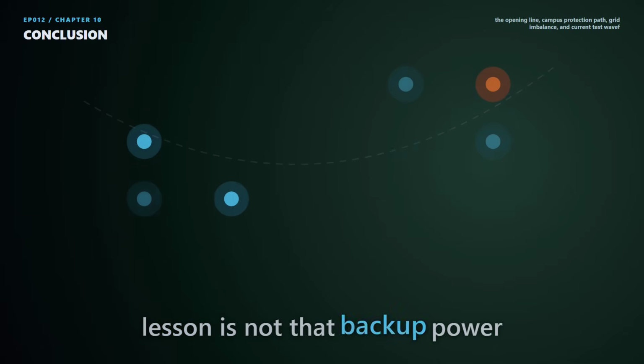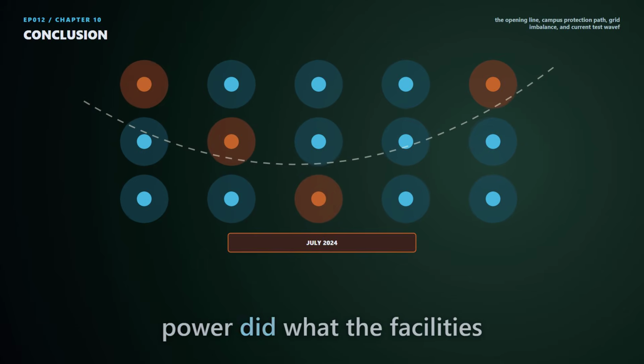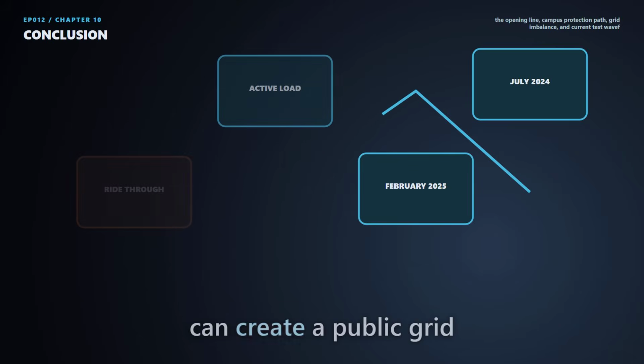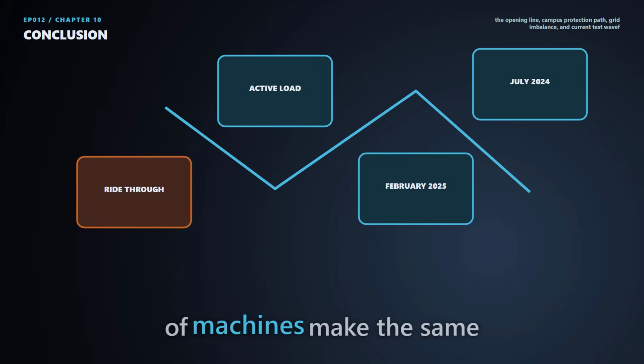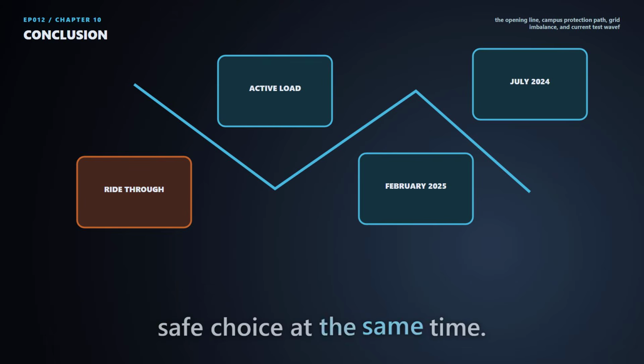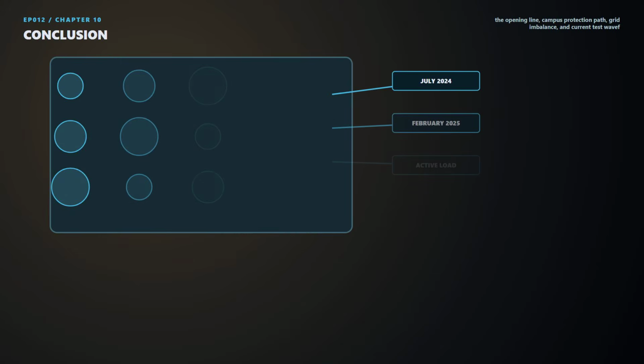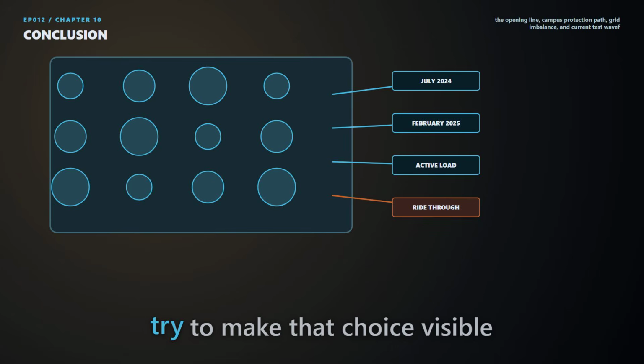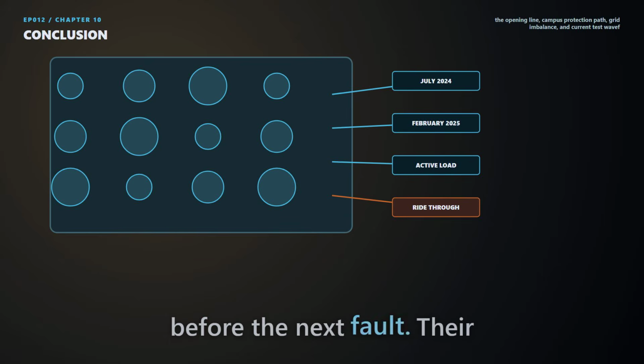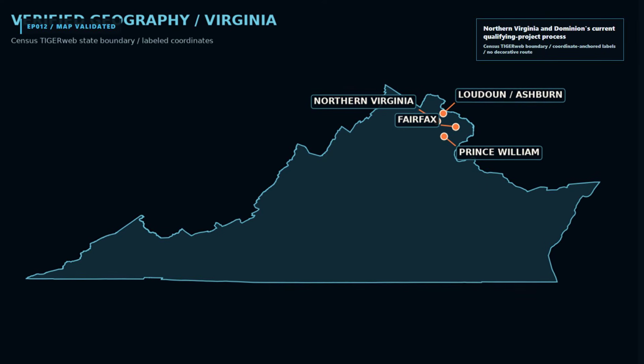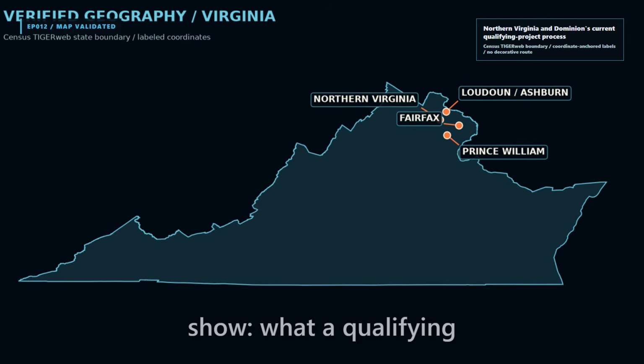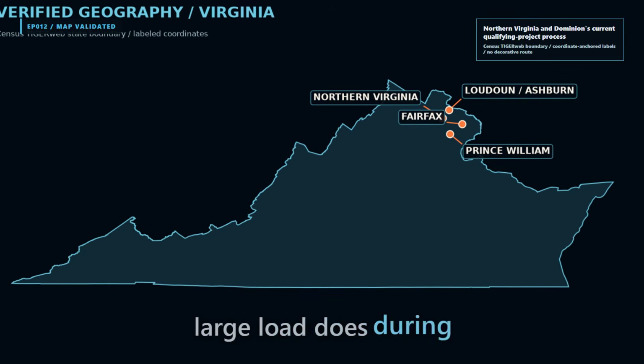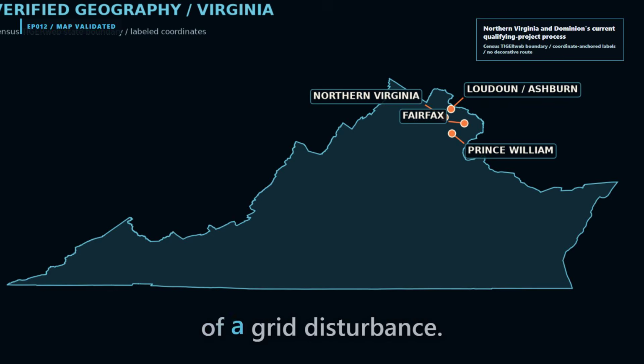The lesson is not that backup power is the enemy. Backup power did what the facilities expected. The lesson is that private resilience can create a public grid event when thousands of machines make the same safe choice at the same time. Dominion's April 2026 interconnection requirements try to make that choice visible before the next fault. Their success will depend on a detail that peak demand alone cannot show: what a qualifying large load does during the first 100 milliseconds of a grid disturbance.